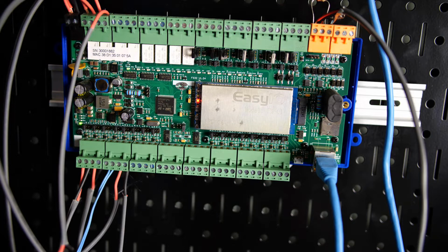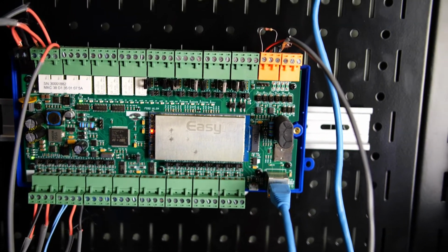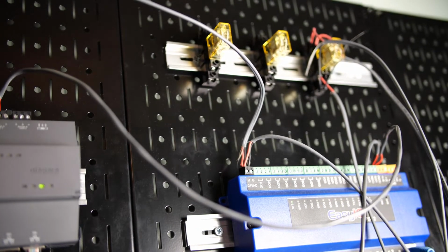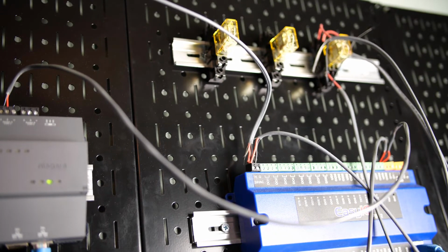That's why oftentimes when I'm first teaching my technicians, I say, hey, guys or gals, when you're doing actual control of contacts out in the field, maybe you're trying to pull in a coil or energize a coil for something out in the field, or maybe you're communicating power to something out in the field, I really recommend using relays. Now there's those relay in a box, as I mentioned, and as I showed yesterday, there are these IDEC relays up here, which are simply just regular 2-pole relays, just normal relays. And if you're wondering what is a pole, what is a coil, what is a contact, we're going to have an electrical video where we go through all this stuff, because I know yesterday we talked about shared commons and separate commons, and some of that stuff's not going to be familiar to you.